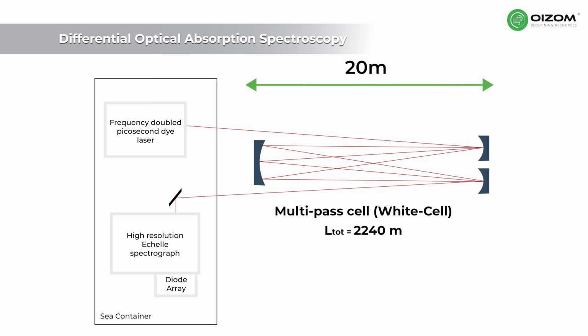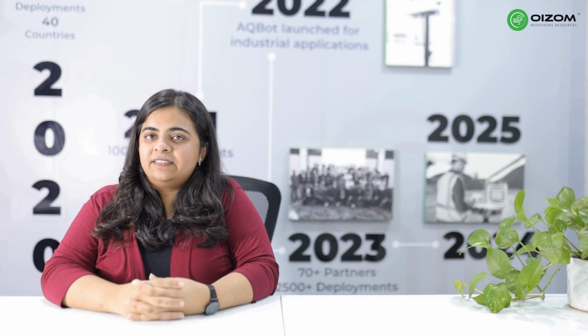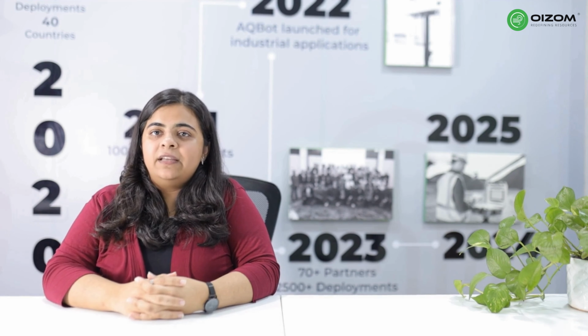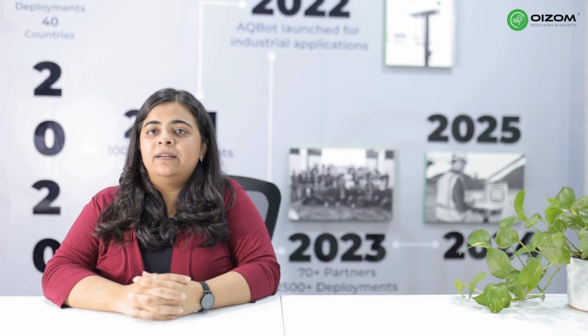5. Differential optical absorption spectroscopy, DOAS. Used for large areas, DOAS sends light over long distances. NOx gases absorb some of this light, and the analyzer measures what's missing to calculate gas concentrations.